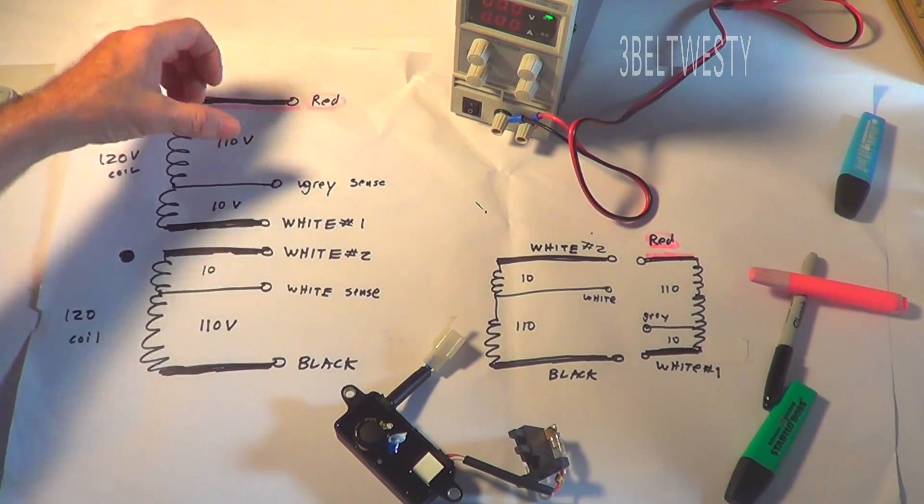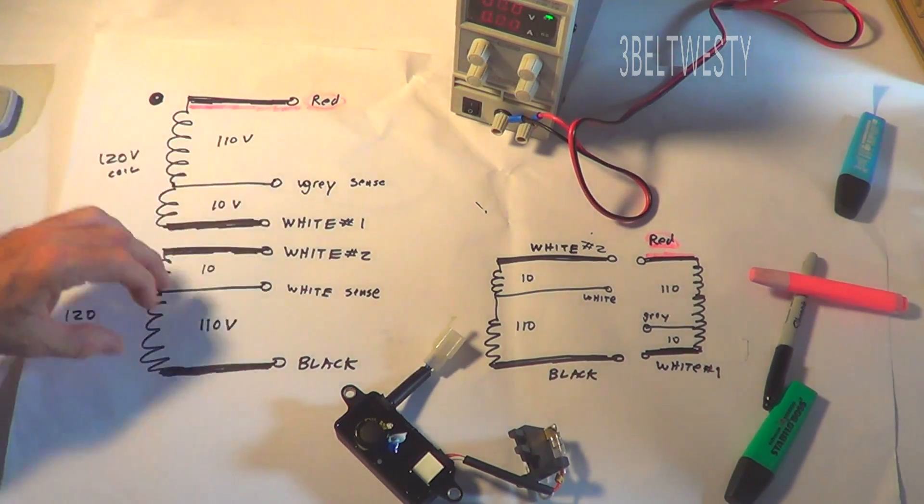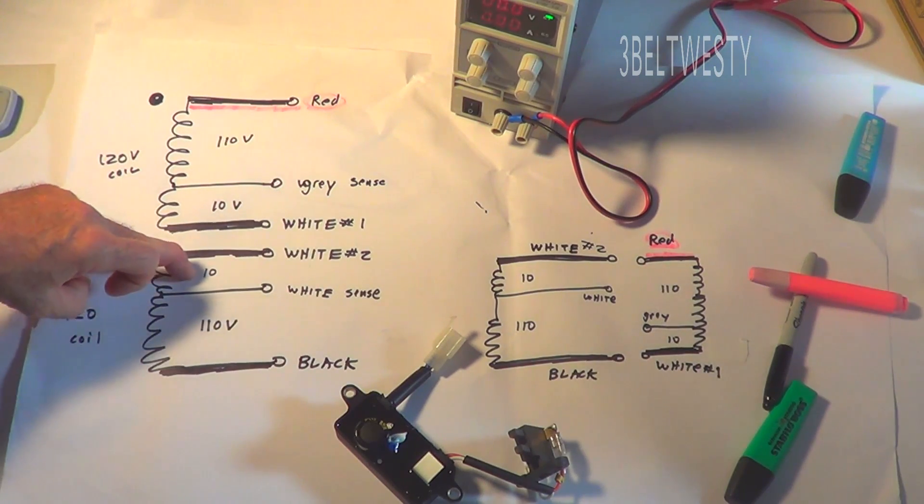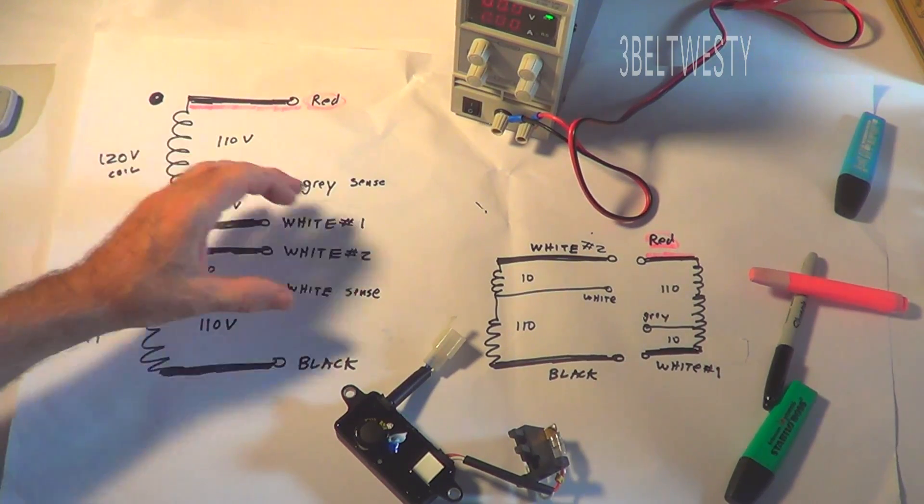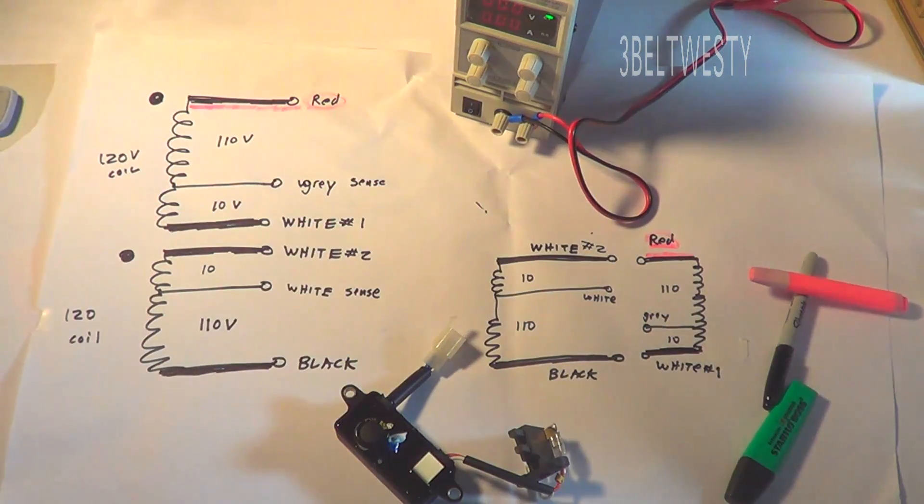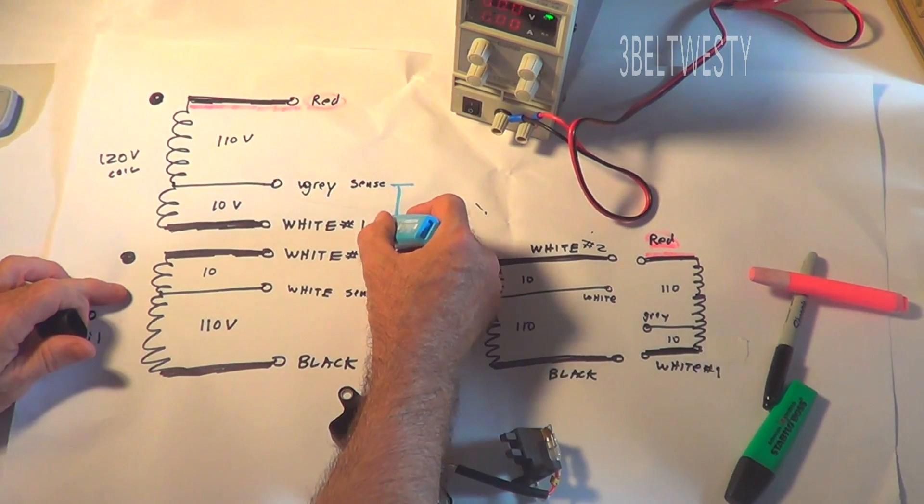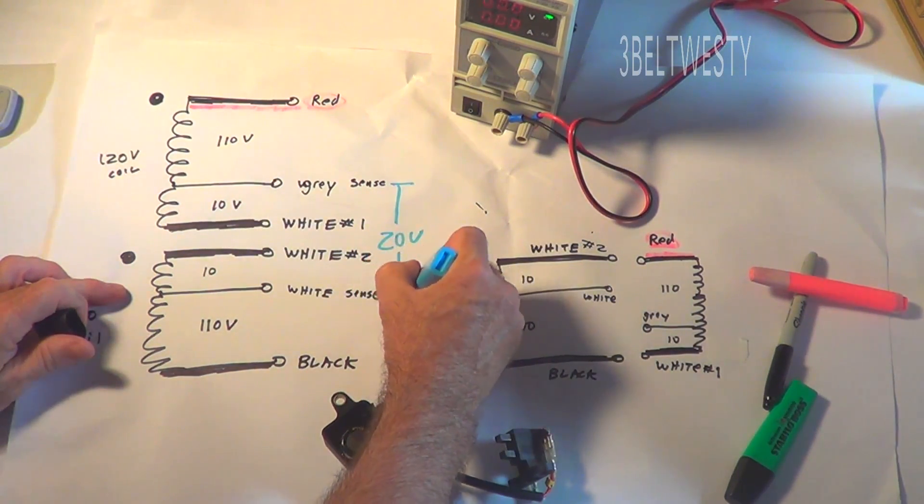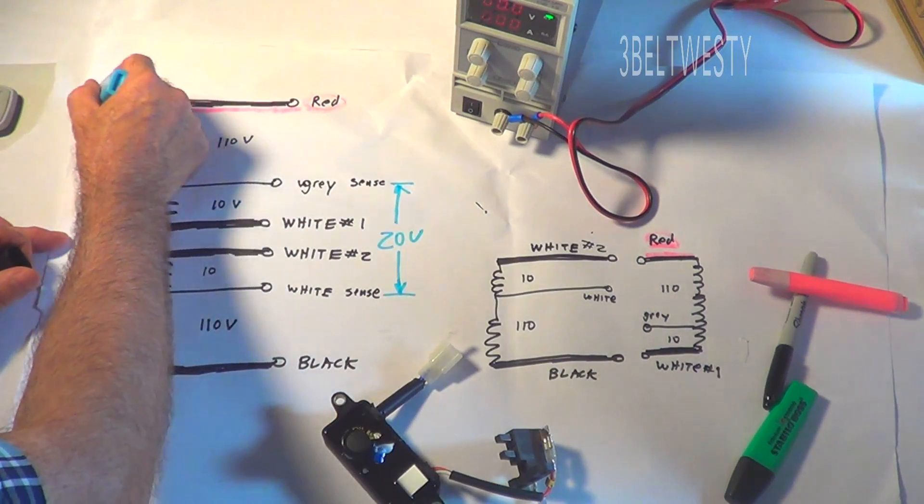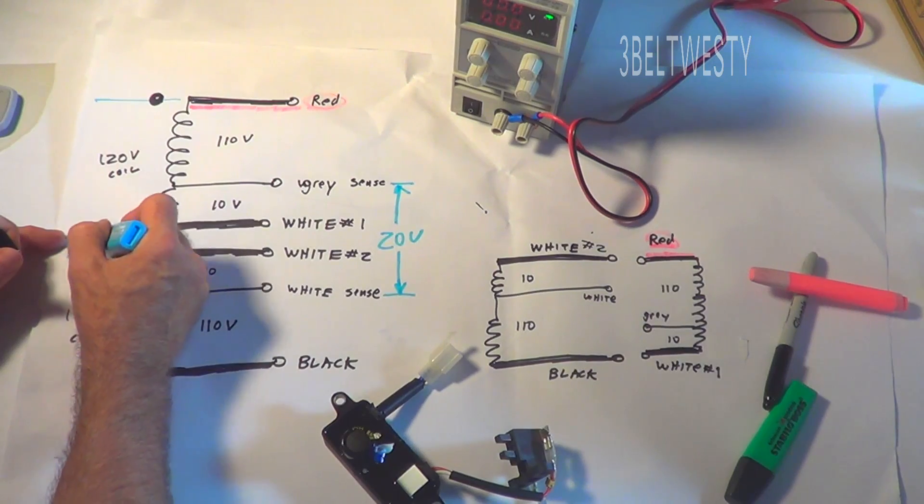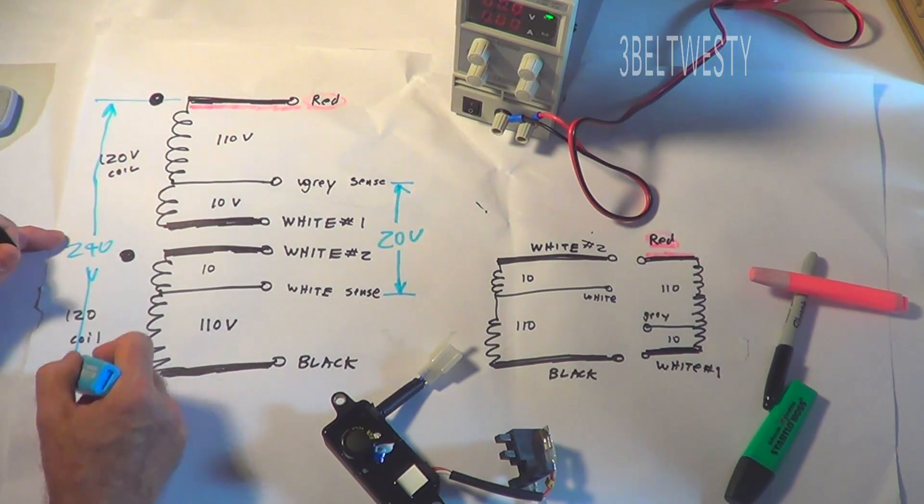The AVR here, which is the control, controls the voltage on that and looks at the two sense wires, the gray and the white. Just for argument's sake, there's roughly about 10 volts across this wire set, 10 volts on this tab. So when it's running here across the two senses, it's roughly about 20 volts in the stock condition.